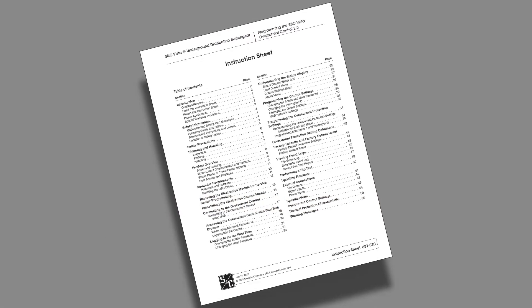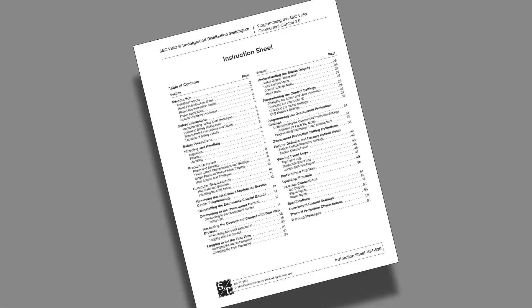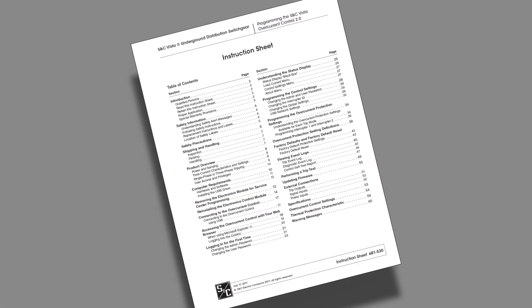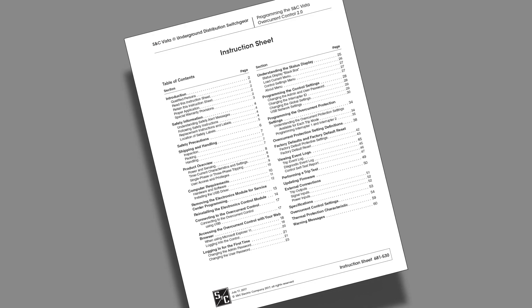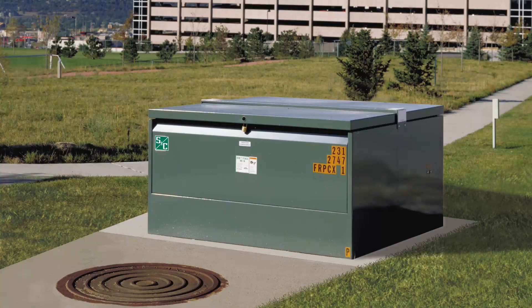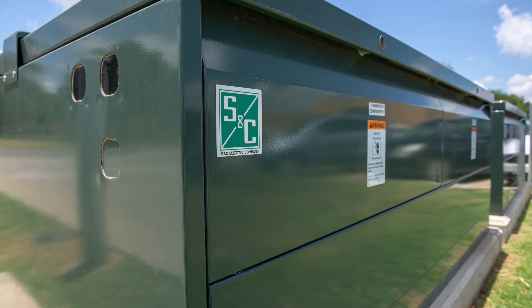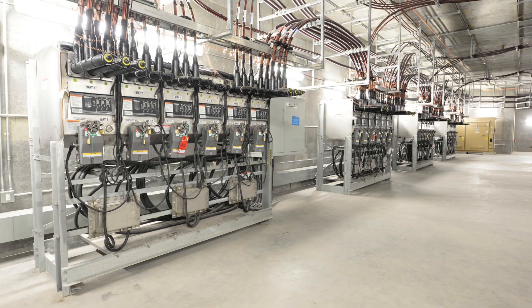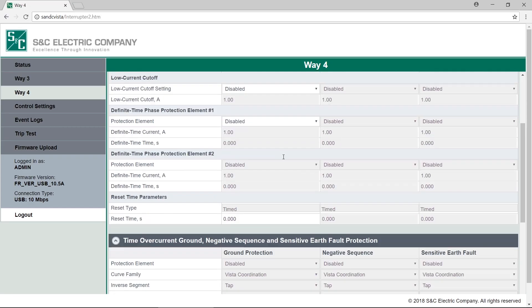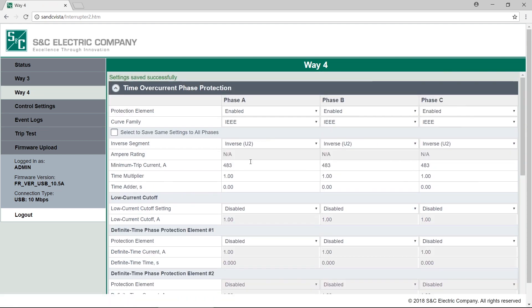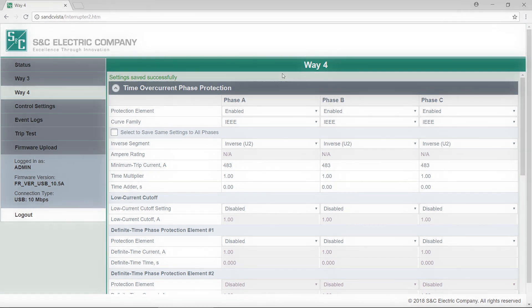This video is intended to be used in conjunction with written instructions 681-530 and 695-535. Vista and Vista SD Underground Distribution Switchgear furnished with fault interrupter ways includes a unique microprocessor-based overcurrent control that detects faults and initiates operation of the resettable fault interrupters. The software is easy to use and allows you to program the control using your personal computer via an easily connected USB port. In this video, we'll show you how to connect a PC to the control, give an overview of the software, and everything you need to do on the control before energizing the switchgear.